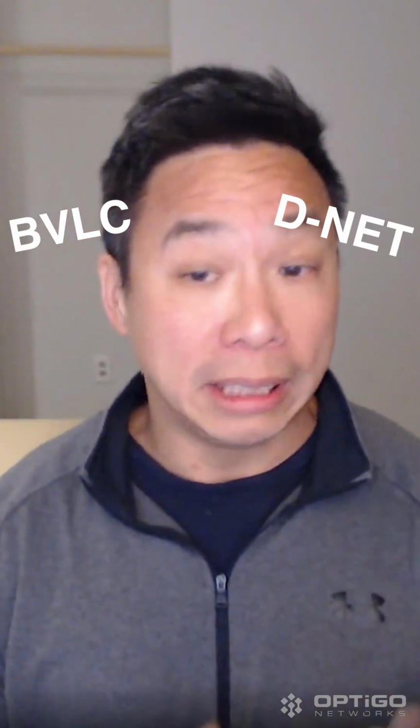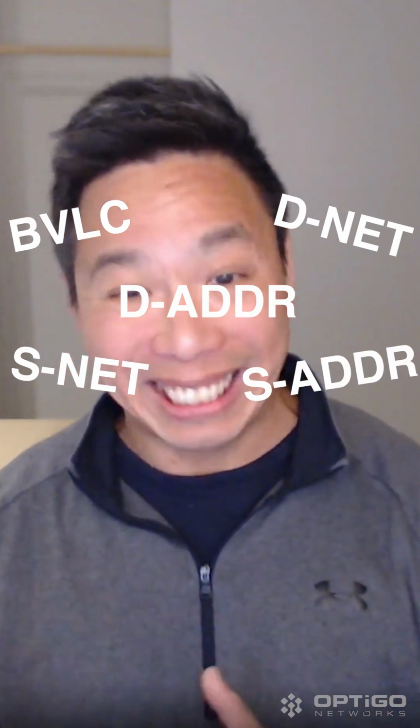Okay, great question. This is where we get into the different nomenclatures and shortcuts that we use in the BACnet world. Sometimes you hear someone talk about a BVLC or DNet or SNet or SAdr or DAdr. It's just because a few of us have been working in the world of BACnet so long that we're short-forming destination network into DNet, and SNet from source network. These are different fields, part of a BACnet packet, more particularly part of the network protocol of the BACnet standard. But it's a way to say this packet is going to this BACnet network.